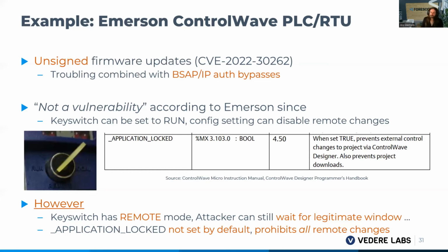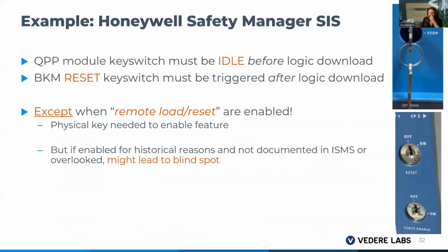And then it's left to the individual discipline of the engineer, which puts a lot of risk on potential human failure. The other option that they have is the application lock setting. The problem there is that it is not set by default, so you need to dig into the manual and set this setting during commissioning, and that essentially disables all remote engineering. So that makes the decision like, look, we don't do remote engineering on this particular PLC, which is sacrificing a lot of engineering effort.